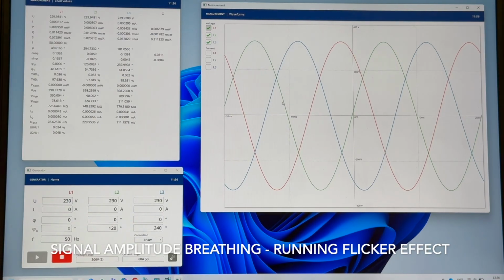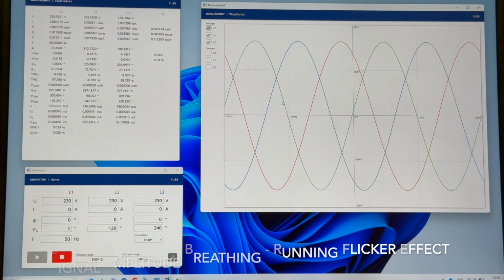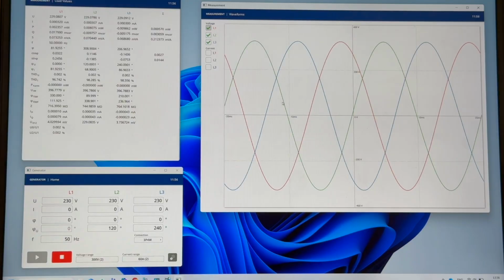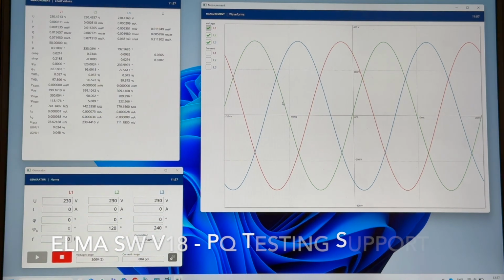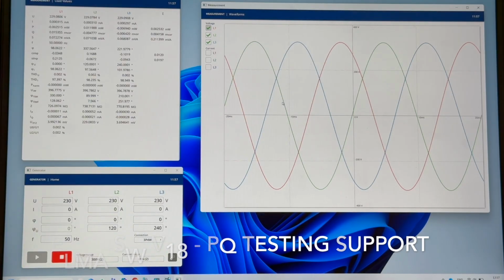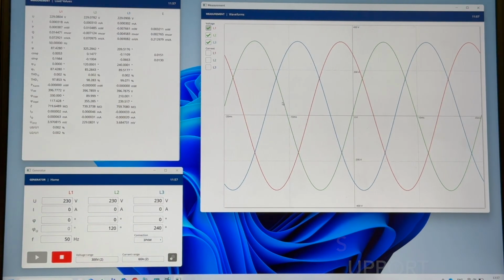and the ELMA control software provides all those features. You can define all test sequences, all tests to measure the meter accuracies, verify the meter on no load, starting current test, DL test, maximum demand test, and also the latest versions of the ELMA software, we call it the ELMA software 18 series, provide power quality tests as well. So you can directly define the tests in the software on the computer to make a flicker verification, dips and swells verifications, harmonics, interharmonics, whatever. By that way you can fully test power quality meters in an automatic way.